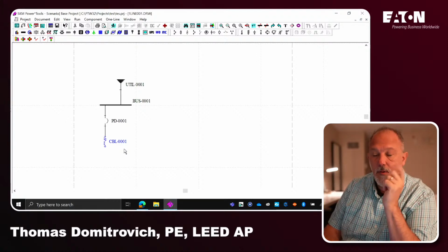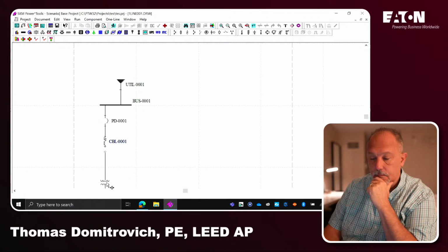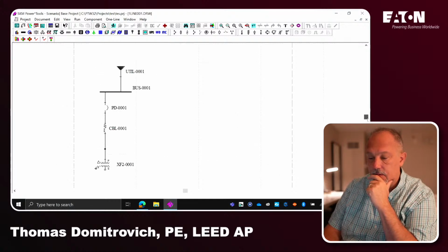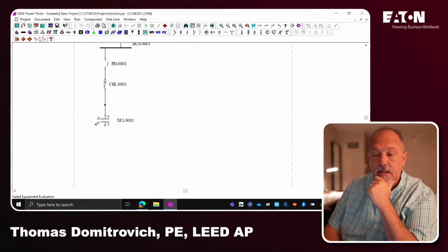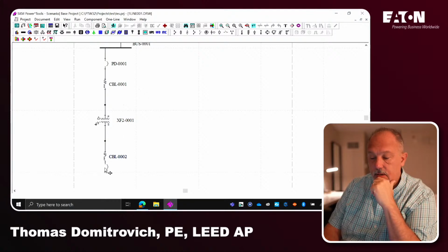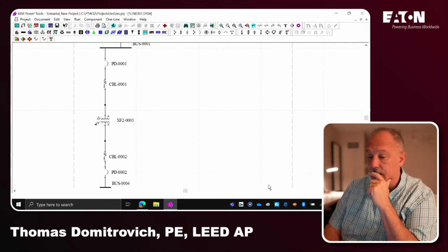We have our conductor, and then remember we were going to a transformer. Boom. I gotta scroll down this way. We put a transformer in, and then we had a conductor on the secondary. And then we had a circuit breaker. There's my circuit breaker. Then I gotta drop it. There it is, I dropped it. And then the circuit breaker was connected to a panel board bus, right? So let's draw that in. There's my panel board, and then I connect that. All right, so there's my one-line diagram.